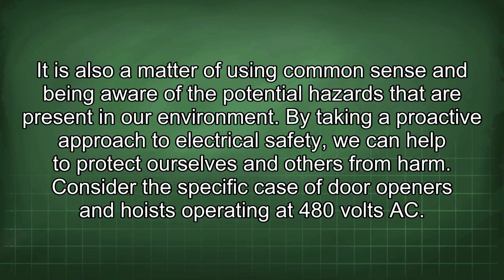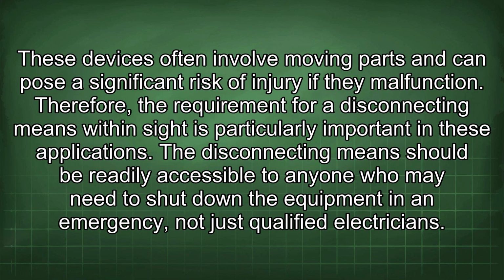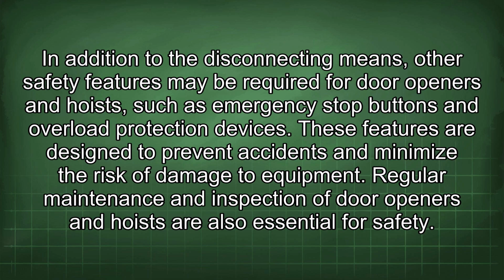Consider the specific case of door openers and hoists operating at 480 volts AC. These devices often involve moving parts and can pose a significant risk of injury if they malfunction. Therefore, the requirement for a disconnecting means within sight is particularly important in these applications. The disconnecting means should be readily accessible to anyone who may need to shut down the equipment in an emergency, not just qualified electricians. In addition to the disconnecting means, other safety features may be required for door openers and hoists, such as emergency stop buttons and overload protection devices. These features are designed to prevent accidents and minimize the risk of damage to equipment.